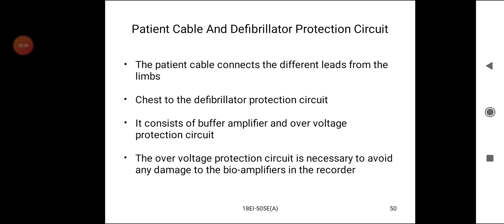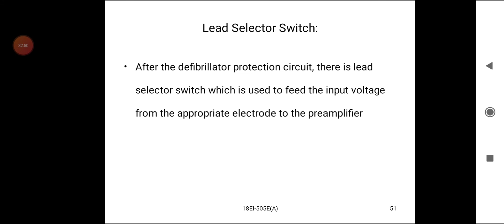Lead selector switch. After the defibrillator protection circuit, there is a lead selector switch which is used to feed the input voltage from the appropriate electrode to the amplifier. The calibrator. A push button allows the insertion of a standardization voltage of 1 millivolt to the preamplifier. The ECG signal goes to the bioamplifier.